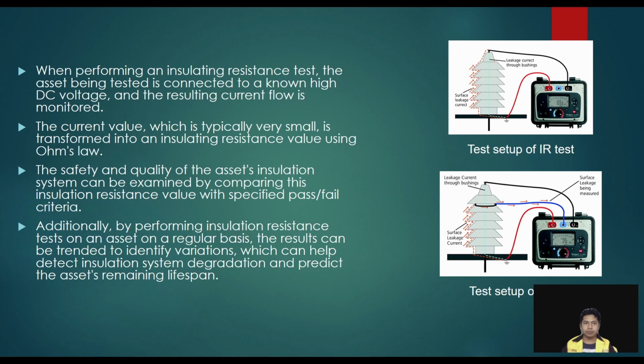Okay, moving on. So this is performing an insulation resistance test. The asset being tested is connected to a high DC voltage and the resulting current flow is monitored. The current value, which is typically very small, is transformed into an insulation resistance value using Ohm's law. So the safety and quality of the asset insulation system can be examined by comparing its insulation resistance value with a specified value, which gives a pass or fail result. Additionally, by performing insulation resistance tests on an asset on a regular basis, the results can be trended to identify variation, which can help detect insulation degradation and predict the asset's remaining lifespan.